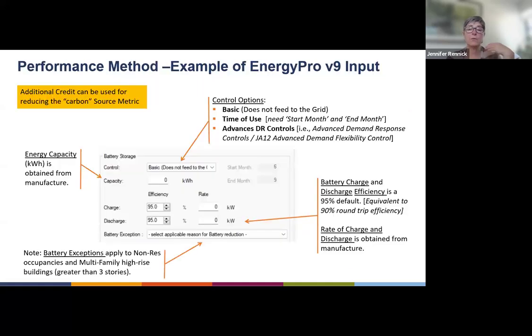As background, when you're working with your energy consultant, some of the inputs we'll ask for on these battery systems, whether from the mechanical engineer, architect, or PV and battery consultant, otherwise we'll put in placeholders. We'll want to know battery charge and discharge efficiencies, the rate of charge and discharge, and whether the project will have basic controls or engage in time-of-use controls as part of the grid stabilization PG&E is doing, or whether it includes advanced demand response controls to meet JA12 demand flexibility requirements.